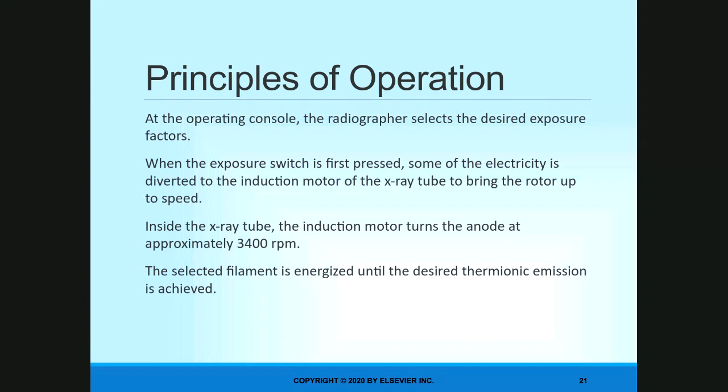All right, and remember, your focal spot size determines which filament actually heats up. So when you press the rotor exposure switch, the anode starts to spin up to speed, and the cathode starts to heat the filament that you chose to release electrons to make an electron cloud, which will come across and smash into the anode.